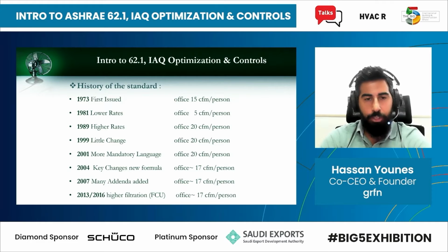Once we had the energy issue in the US with the oil embargo, they thought of ways to reduce energy consumption, and they said, well, why don't we just reduce the outdoor air ventilation? That will reduce the consumption of our fans and our cooling and heating systems. And they went drastically from 15 to 5, which was, I would say, too low.